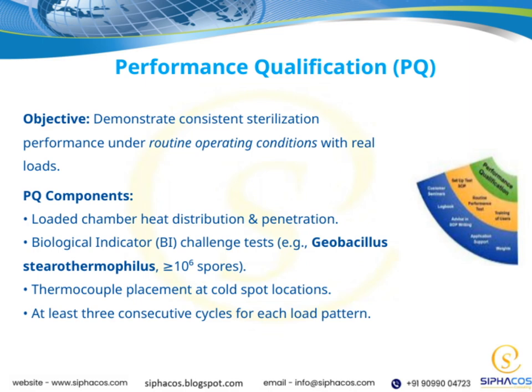Placement of thermocouples is also critical. We position them at cold spot locations, areas that tend to be the most challenging to sterilize, to make sure the process is effective throughout the chamber. And finally, we perform at least 3 consecutive cycles for each load pattern to confirm consistency and reliability over time. All of these steps work together to validate that our sterilization process is robust and dependable, which is essential for maintaining safety and compliance in our operations.